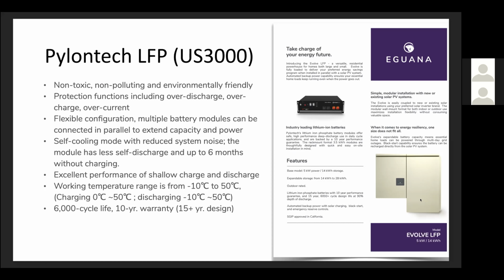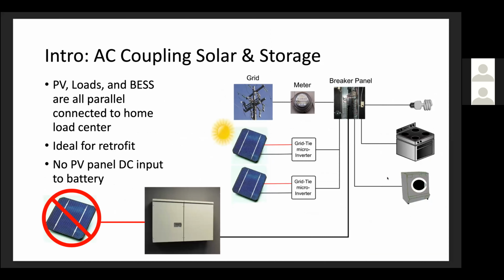The LFP battery cabinet is slightly larger than the inverter cabinet. Okay, a quick look or an introduction to AC coupling, solar, and storage. To most people by now, this is pretty basic stuff, but if you're new to batteries or to AC coupled batteries, if you've only done DC coupled batteries, then this is a quick intro to AC coupling. It just basically means that the PV, the loads, and the BESS, the battery, are all parallel connected to the home load center, functionally anyway.